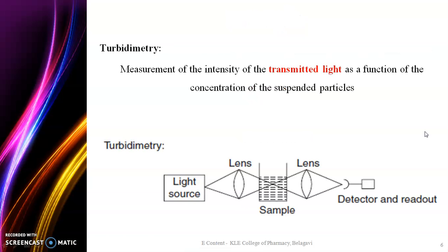Turbidimetry involves the measurement of the intensity of transmitted light as a function of the concentration of suspended particles. The light source emits radiation which is absorbed by the sample, and whatever light is transmitted will be detected by the detector that is placed at the end.